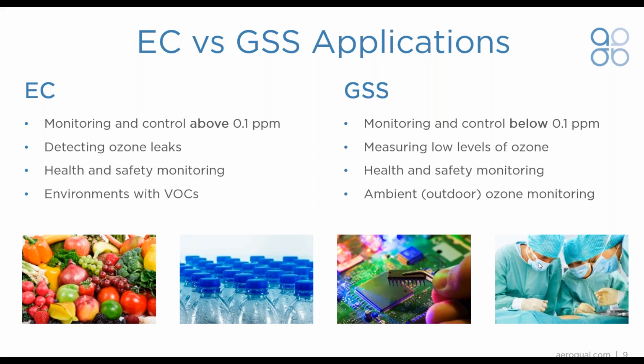Typically, health and safety exposure limits for ozone are between 0.07 and 0.1 ppm over about 8 hours, and they can go as low as 0.05 ppm for short-term exposure. Short-term exposure can be 20 minutes or 15 minutes, or it could be derived by the type of work you're doing, such as heavy lifting or the amount of exertion in your workplace. These really low levels show why the GSS sensor is the best choice for these types of applications.